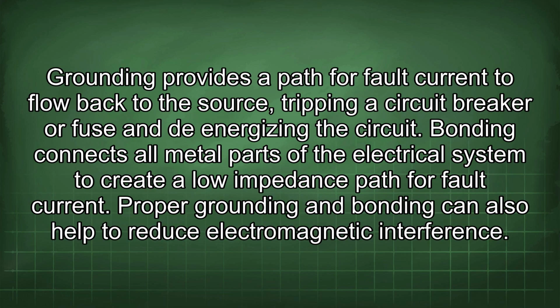Grounding and bonding are critical for preventing electrical shock hazards and minimizing the risk of ignition. Grounding provides a path for fault current to flow back to the source, tripping a circuit breaker or fuse and de-energizing the circuit. Bonding connects all metal parts of the electrical system to create a low impedance path for fault current. Proper grounding and bonding can also help to reduce electromagnetic interference.